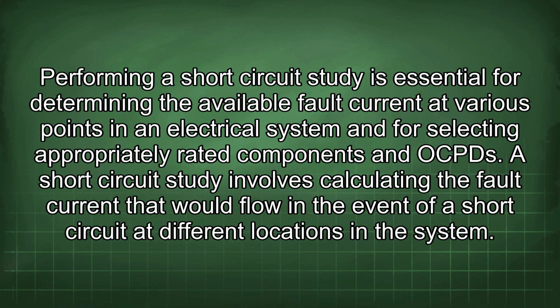Performing a short circuit study is essential for determining the available fault current at various points in an electrical system and for selecting appropriately rated components and OCPDs. A short circuit study involves calculating the fault current that would flow in the event of a short circuit at different locations in the system.